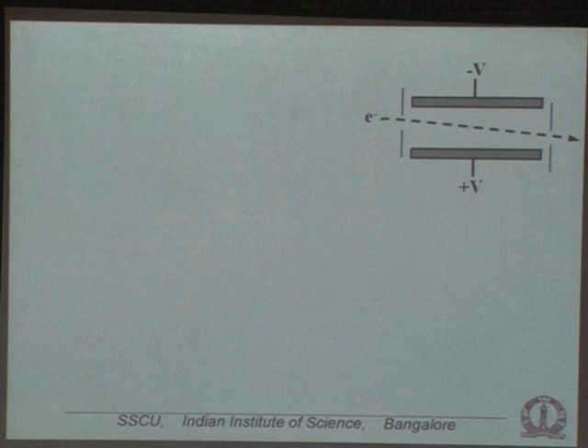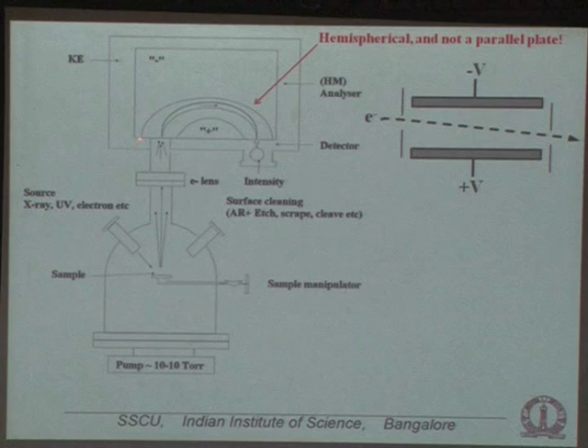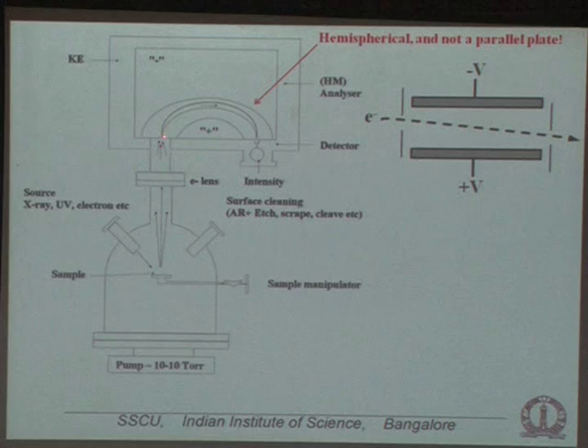In practice, the parallel plate capacitor is made hemispherical rather than flat, for technical reasons. In the hemispherical analyzer, you have two hemispherical surfaces with a gap between them — negative voltage on the outer hemisphere, positive on the inner. Electrons enter from one side. The hemispherical geometry provides spatial focusing: electrons with the same kinetic energy but entering at slightly different angles are refocused, so no electrons of that kinetic energy are lost. This is the key technical advantage.